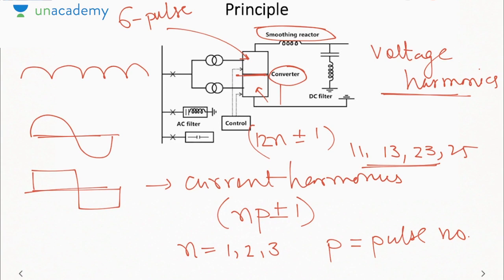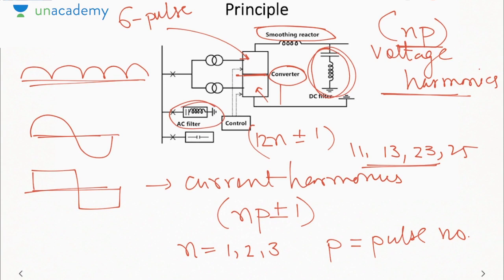And the voltage harmonics will have an order of NP, where N is an integer 1, 2, 3, and P is the pulse number, because in a 6 pulse converter we will have 6 pulses. Okay, so the first harmonic will be the 6th harmonic. And here we are using a DC filter, again to smoothen out the DC voltage waveform. Here the AC filter is used to reduce the current harmonics on the AC side. As I told you, in a rectifier we will have current harmonics on the AC side.